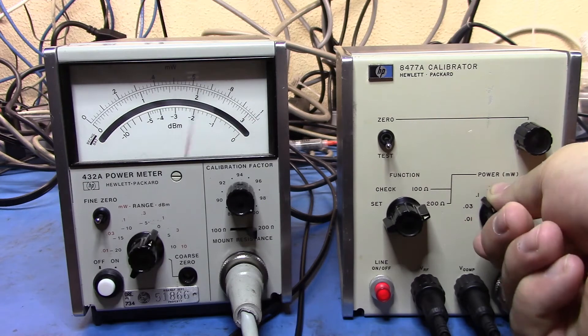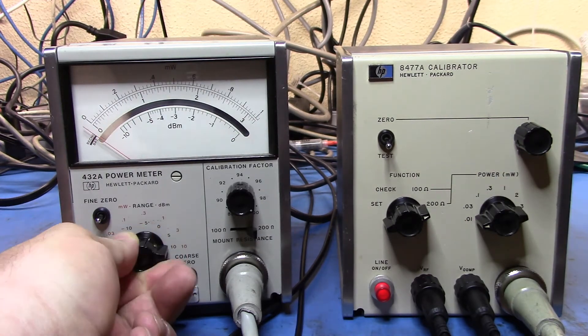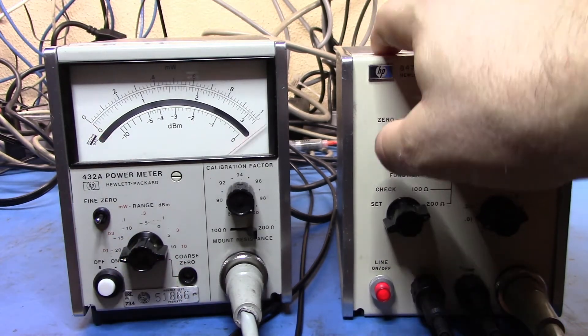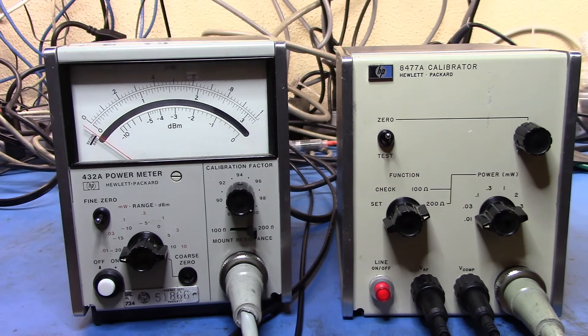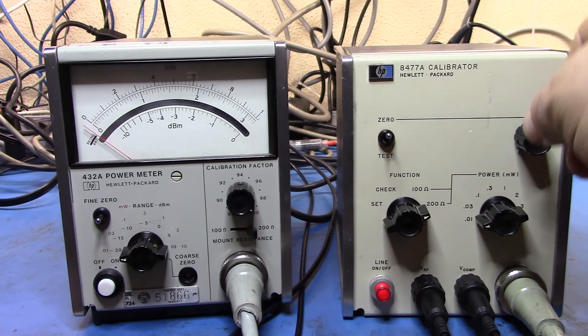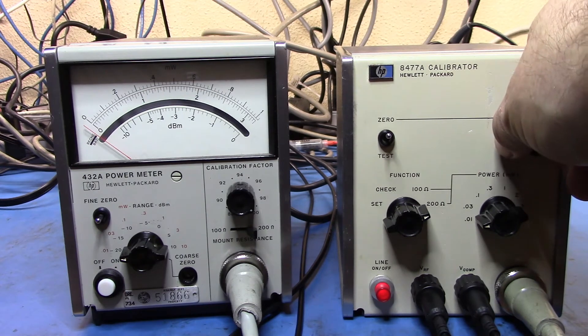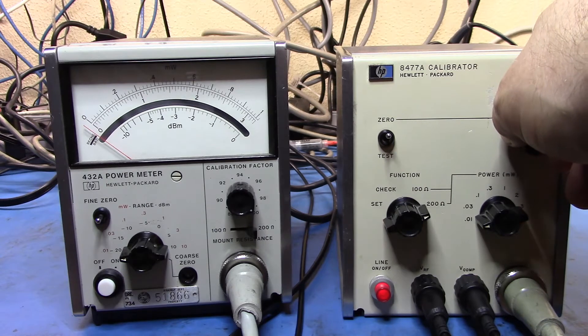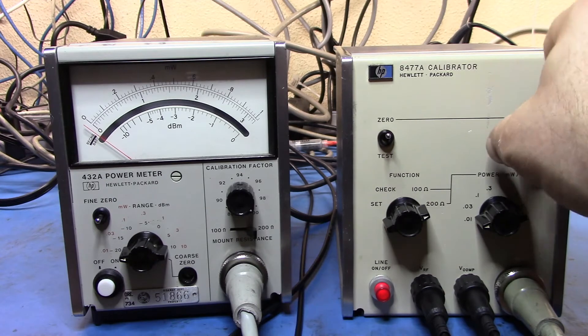All right. So now what it says that we need to do to get this to work is we're going to come down here to point one. I'm going to set this to zero. And then what I have is I have this cable here. This is connected up to a DVM. And so now with this set to zero, I need to change the output of the DVM until I get zero volts. Oh, there we go.